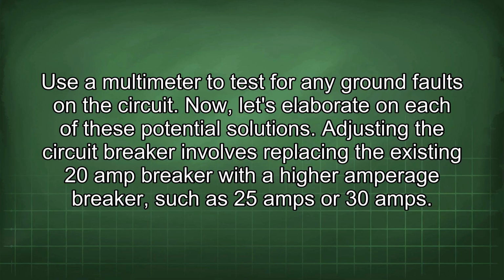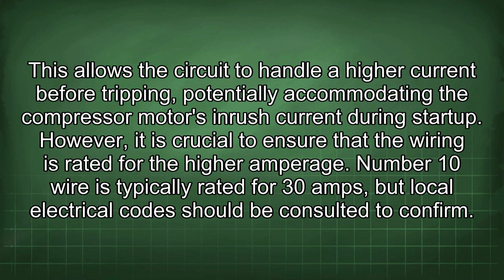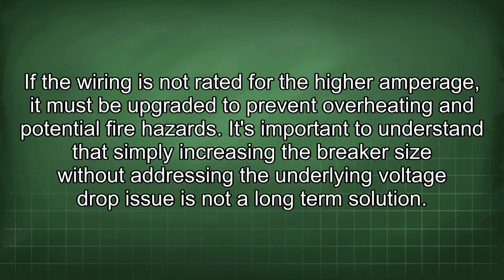or 30 amps. This allows the circuit to handle a higher current before tripping, potentially accommodating the compressor motor's inrush current during startup. However, it is crucial to ensure that the wiring is rated for the higher amperage. Number 10 wire is typically rated for 30 amps, but local electrical codes should be consulted to confirm.